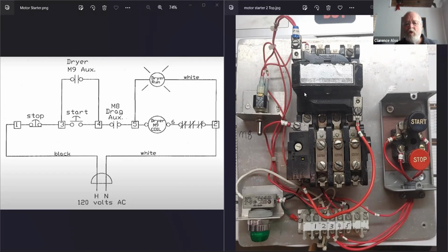So those two things are in parallel with each other, kind of. Now that light could have been wired to the other side of the coil, so that whenever the coil came in, the light would come on. But this isn't how they wired it up - they wired it right where it went to neutral. So you could push that start button and the coil maybe wouldn't come in because the overloads had kicked out, but the light would still come on.